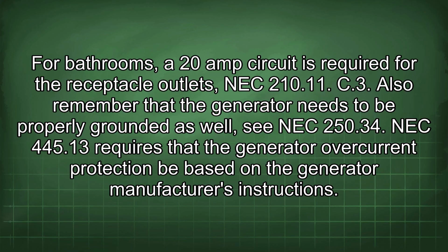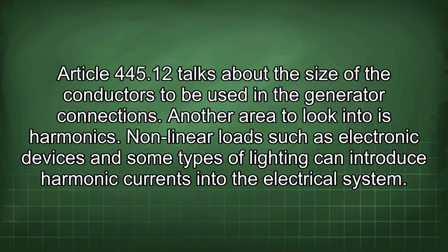NEC 445.13 requires that the generator overcurrent protection be based on the generator manufacturer's instructions. Article 445.12 talks about the size of the conductors to be used in the generator connections. Another area to look into is harmonics. Nonlinear loads such as electronic devices and some types of lighting can introduce harmonic currents into the electrical system.